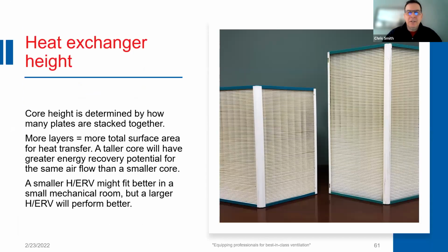Now, the number of plates stacked together impacts the overall height of the heat exchanger. And the higher the heat exchanger, the bigger the heat exchanger, the more surface area there is. For the same amount of airflow through a smaller versus a larger heat exchanger, you will get less versus more energy recovery. And so devoting some real estate to the size of the device actually provides better recovery effectiveness. So you want to make some space in the building plan for the HRV or ERV. You'll get better performance.